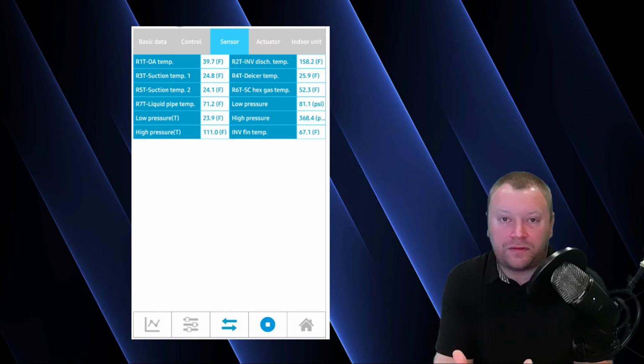See, we also have to manage the discharge pipe temperature. If you throttle down your outdoor expansion valve too much, then you have less refrigerant flowing through your outdoor heat exchanger, and therefore your compressor's discharge pipe temperature is going to go up. So we're balancing the pressures on both the high and the low side to make sure everything can hit targets. Those EEVs are regulating to make sure we're maintaining subcooling at the indoors, superheat at the outdoor unit, so that everybody plays nicely. And so here we can see that we're going to go through the outdoor heat exchanger.